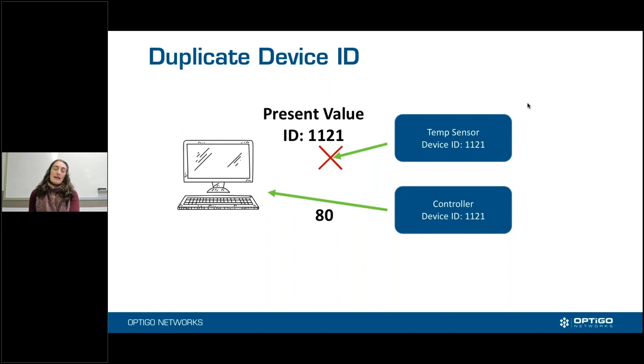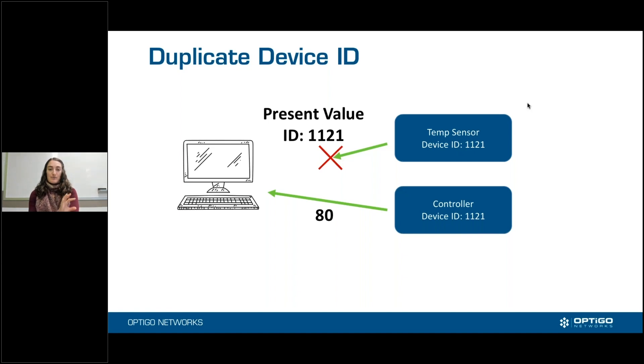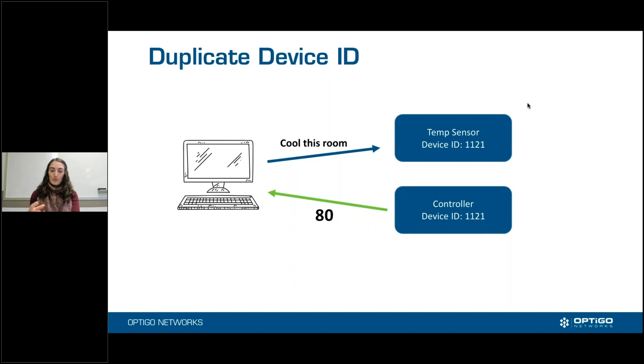So potentially it's trying to ask for the current temperature from the temperature sensor, but the controller responds. In this example, it might be asking for the present value of a specific object ID — maybe object ID 27. And the controller also has an object ID 27, and so it says the present value of object ID 27 is 80. The BMS is thinking the temperature is 80 degrees Fahrenheit, which is way too warm, so it's going to cool the room — but it thinks that's the temperature of the room where the temperature sensor is, so it cools a different room. Very likely that 80 isn't even a temperature — it may be some other unit or value.